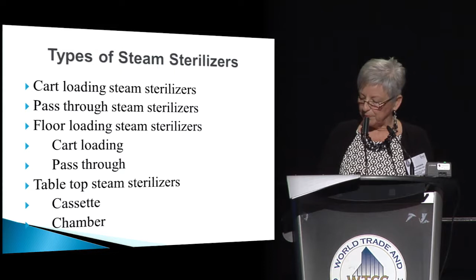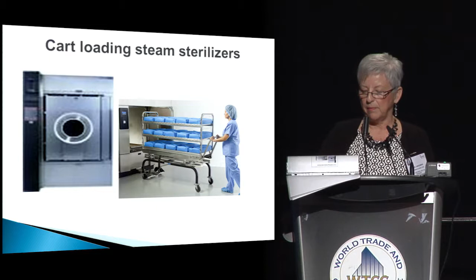The first one is the cart loading steam sterilizer, and this is one of the older models out there, and you'll see a lot of them in the older facilities. It has a handle that you wind around to close. The more modern ones might have a different close handle, but the important thing about this sterilizer is that it is loaded on a cart. A carriage is on a cart, and it's pushed into the chamber and retrieved in the same way. With any sterilizer, tabletop or this size, loading is so important to allow the steam and the air to get around.